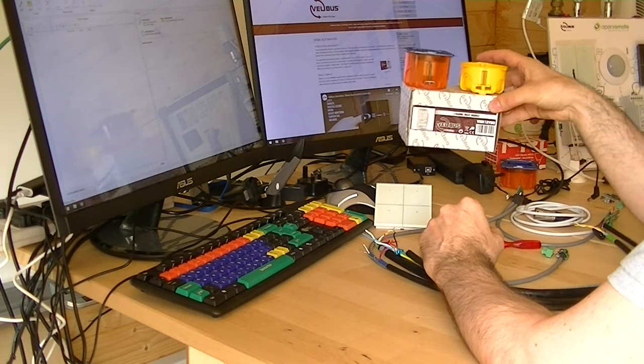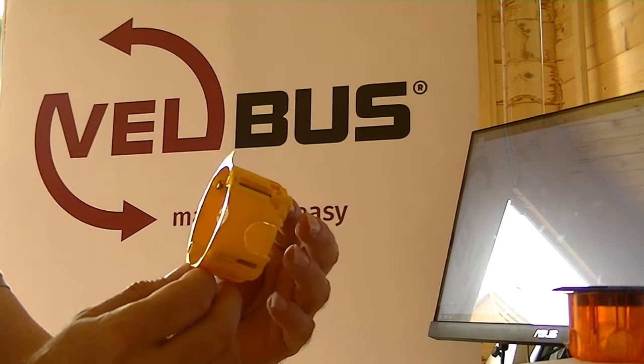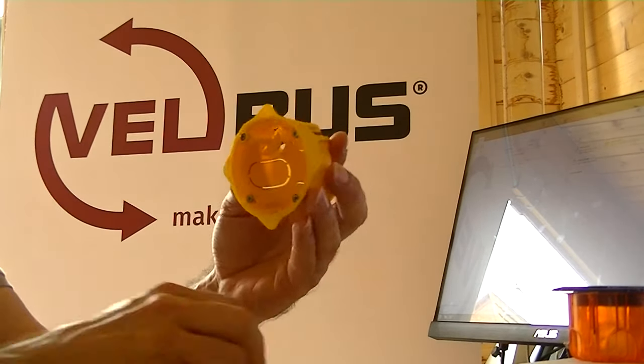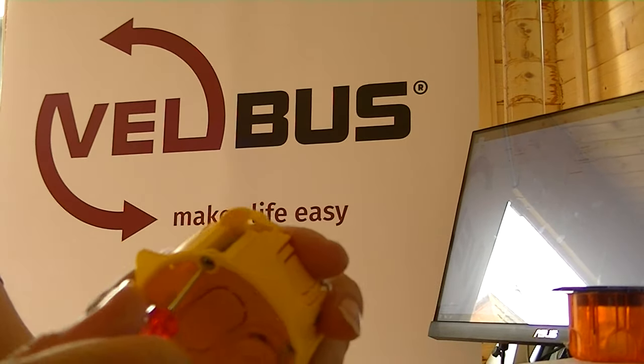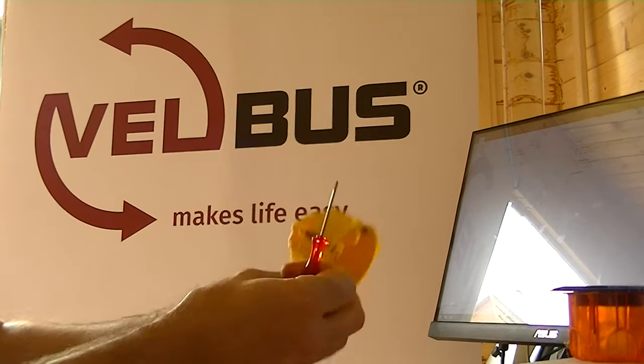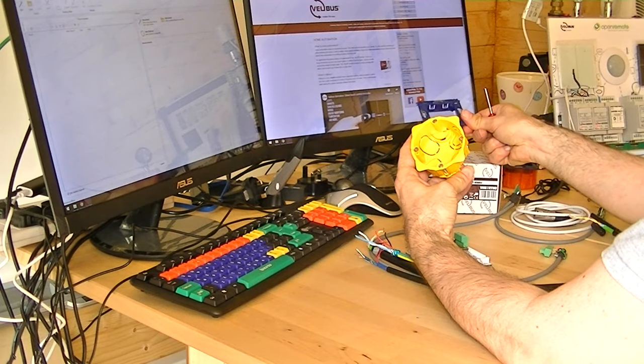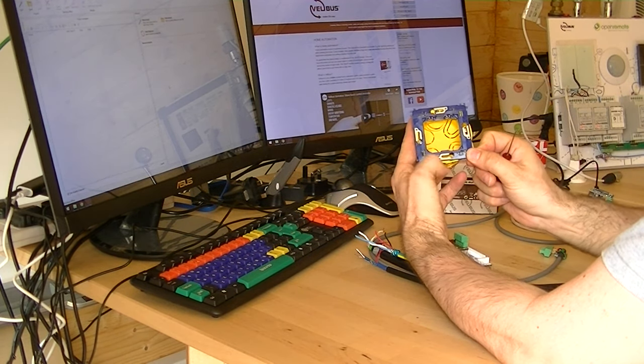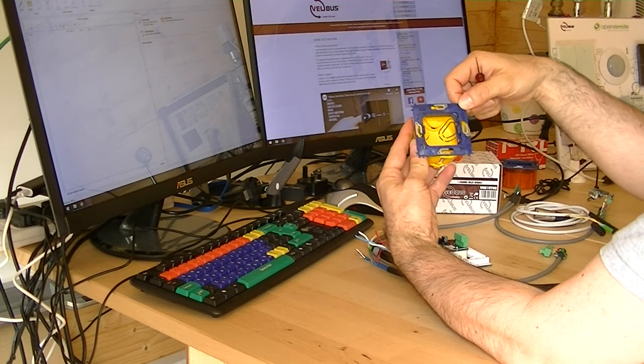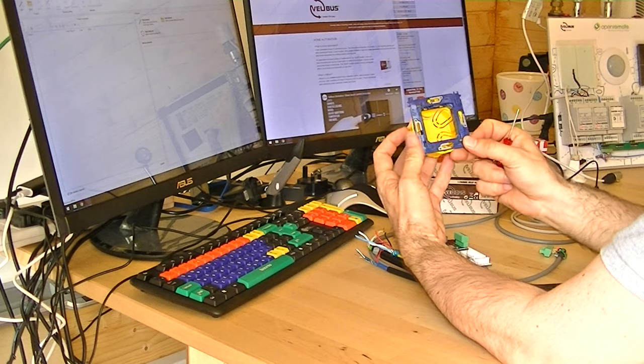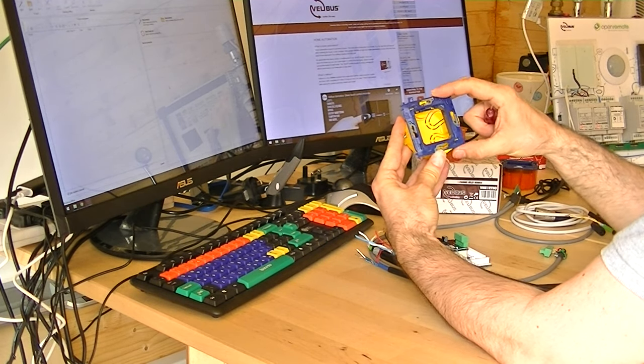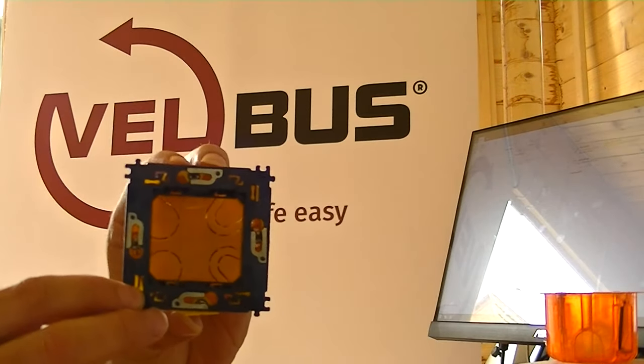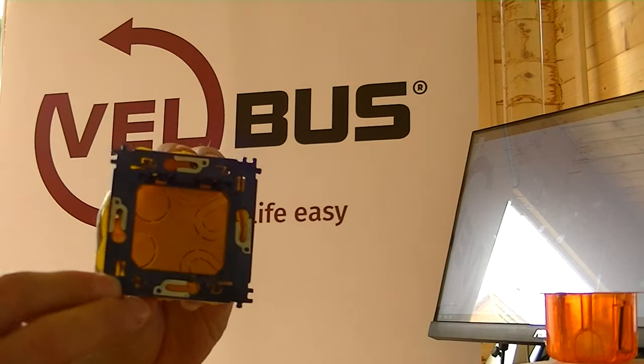So as you can see it's all quite straightforward. You do need to allow about 40mm within the boxes to allow for the wiring and this is a good 40mm unit. This is a Legrand, it's a plasterboard box that we're showing here and it's got plastic lugs at the back which roll out and then tighten up to grip the plasterboard. Each one does require a blue mounting frame to be added to it before the glass panel can be clipped on. The nice thing is there's two orientation options so depending on where your lugs go there's always two screws free for screwing on the mounting frame. The nice thing is you can rotate them around, there's a bit of free play so as long as you've got a round hole you're definitely going to get the glass panel fitted nicely on the wall.